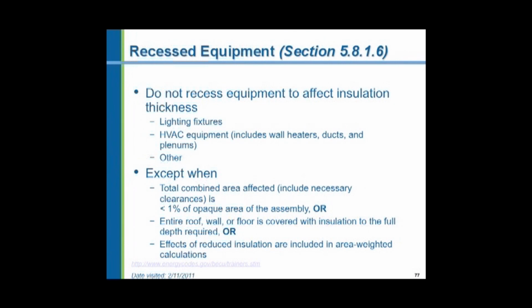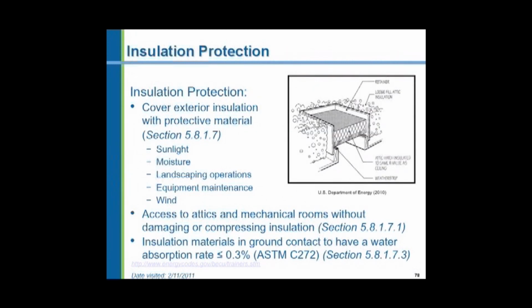Equipment in a ceiling that's insulated is limited. You can put recessed light fixtures in a ceiling. They have to be IC or insulated ceiling rated, but they can be no more than 1% of the area. However, I like to design a building where we don't compromise the insulation at all. We have the full insulation over all of the recessed equipment that punches holes in our insulated ceiling. This is my feeling as a professional engineer, although the code does allow up to 1% of the ceiling area to be exempt. We have to protect the insulation.